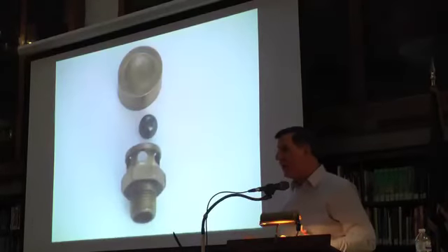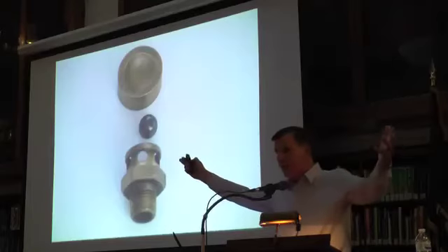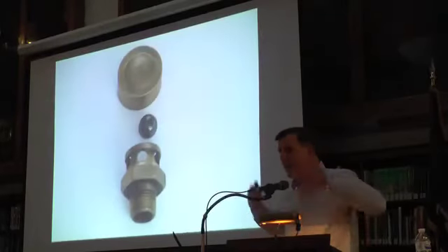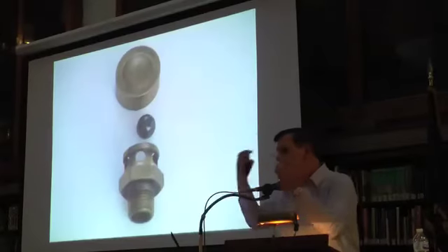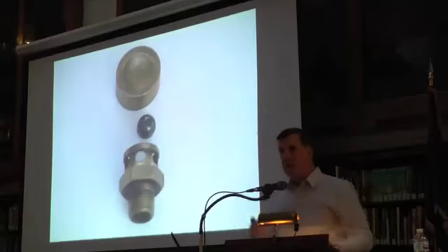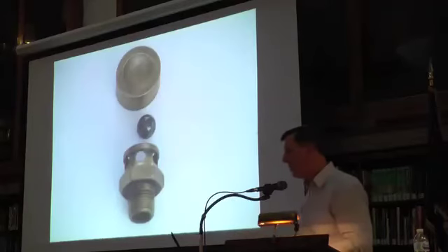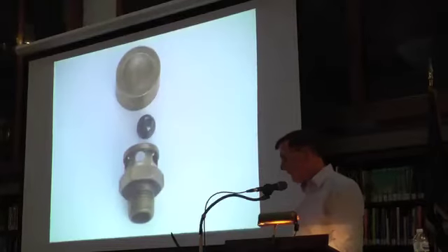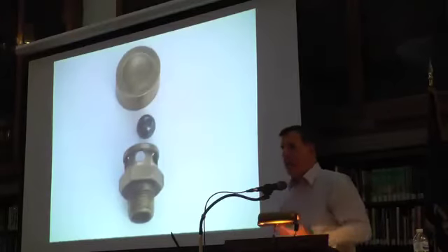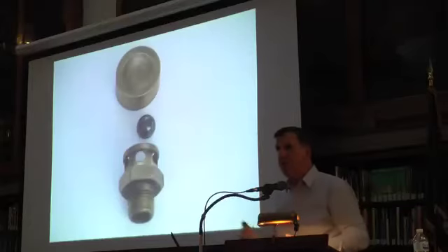On every cycle, they have to expel all the air, and then they fill up again with air when they shut down, and it's breathing in and out. That's why you get rust inside these systems, because everything's wet and you bring air back in on it all the time. So the pipes begin to rust, the radiators begin to rust. All that stuff washes down into the boiler. So I would go in the boiler room and say, if I were air, how could I get out? And then I'd start wandering through the building.